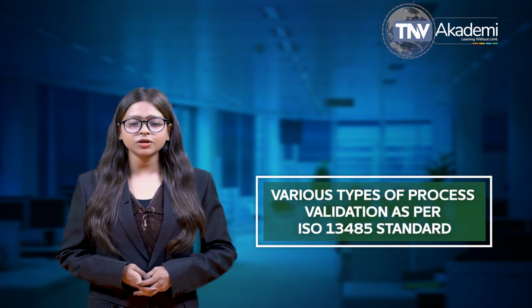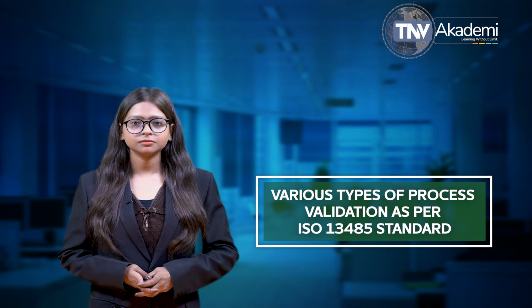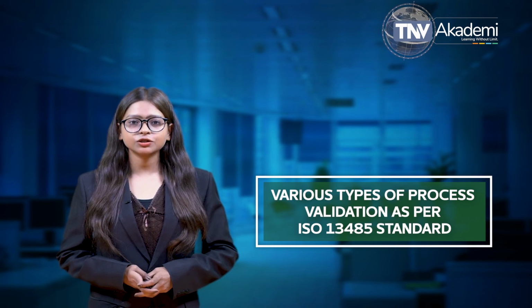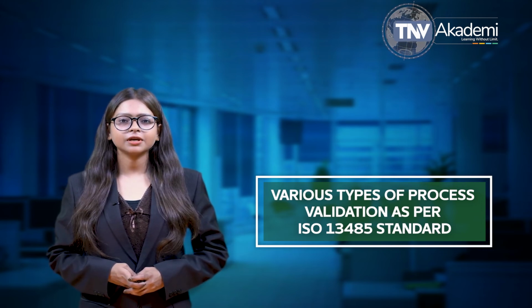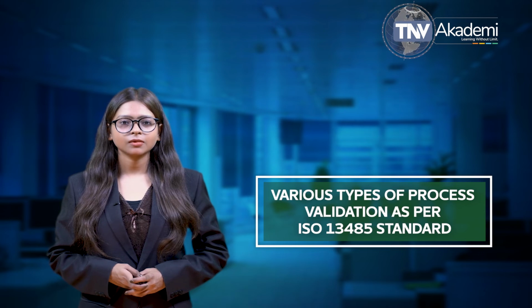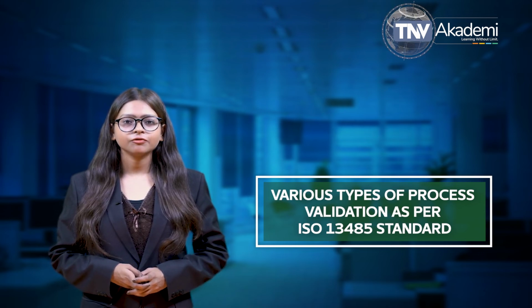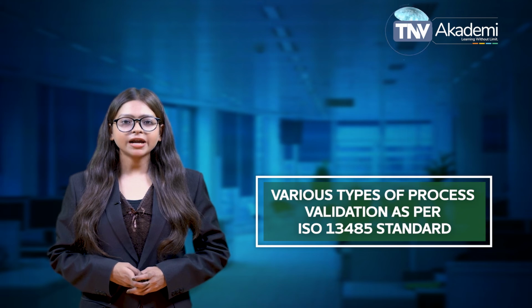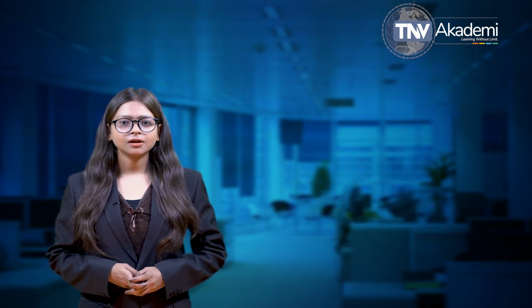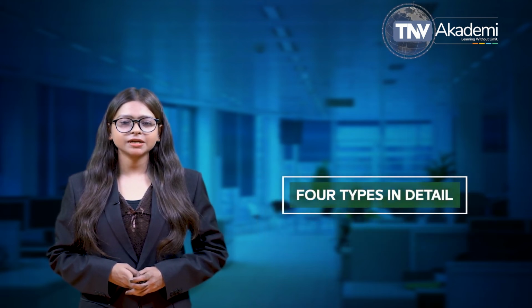And finally, let us now discuss the various types of process validation as per ISO 13485 standard. Process validation is often categorized according to the time it is performed in relation to the production schedule. Based on description, there are 4 types of process validation: prospective validation, retrospective validation, concurrent validation, and revalidation. Let us discuss all the 4 types in detail.